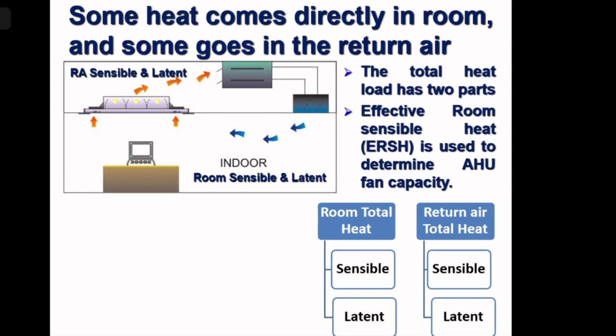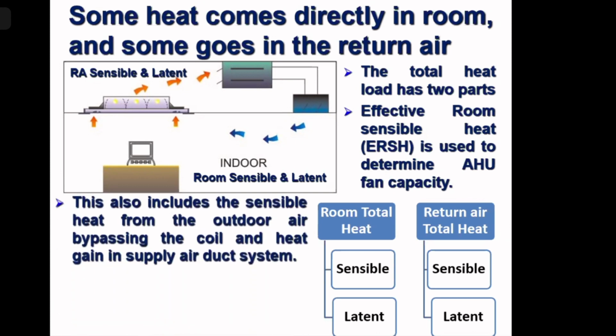And my air handling unit fan sizing is dependent on only the sensible part of the room total heat, which we call effective room sensible heat. So effective room sensible heat, there is a twist at the end. It will be coming in the next line, next paragraph, when Marco shows it. What is effective room sensible heat? Effective room sensible heat, not just the sensible heat being added in the room. This also includes sensible heat from the outdoor air, which bypasses the coil. And heat gain in the supply air ducting.